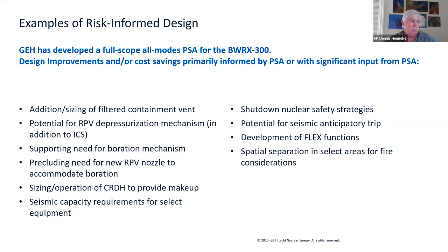But the key ones, I would say, the filter containment vent was important, the need for an additional non-safety-related RPV depressurization mechanism was important. Boration, we're proposing a non-safety-related boration mechanism, a boron addition, just in case there's a rod binding for all control rods. We have multiple ways to drive the rods in, but if that doesn't work, boron addition can be used for that very low-risk scenario.